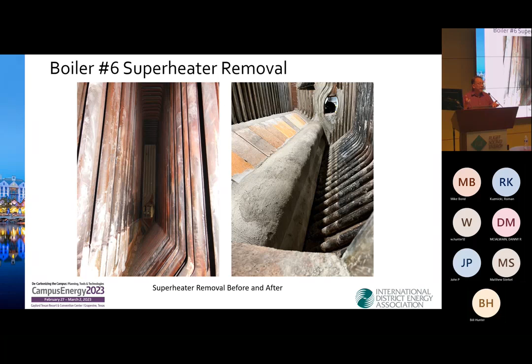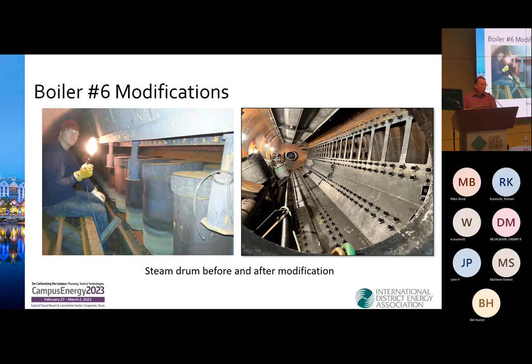This is inside the steam drum. The left image is what it used to look like. Very complex equipment to make sure moisture is not carried out of the boiler. So clean, dry steam. And this is where steam is not the wispy white stuff you might be picturing. Steam is a clear, energetic fluid we're using to power equipment and to heat the campus. But reducing pressure allowed us to simplify the steam drum, so we have a much more open design now. That's on the right.